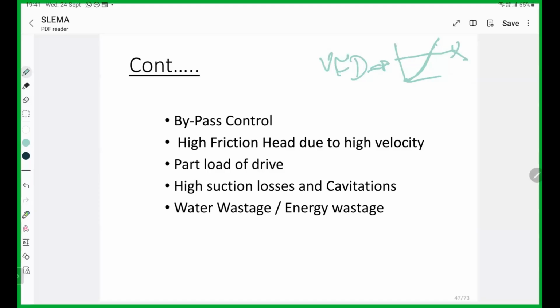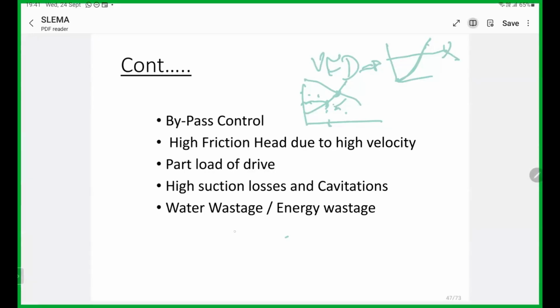Then another thing we have to consider in controlling is impeller trimming, or reduced diameter. Say our system is there, and our actual flow rate is somewhere here. With a VFD application we can reduce the RPM and achieve it, or we can trim the impeller and achieve this flow rate in an efficient way. Right? Two options.